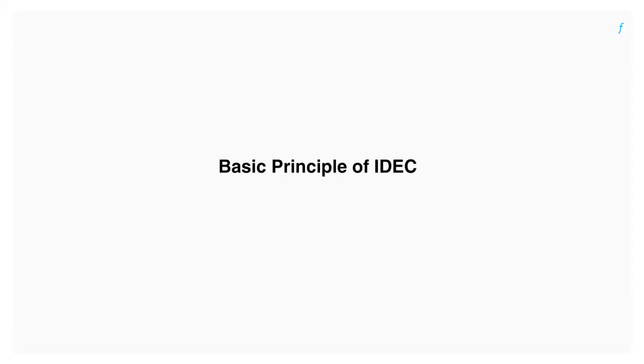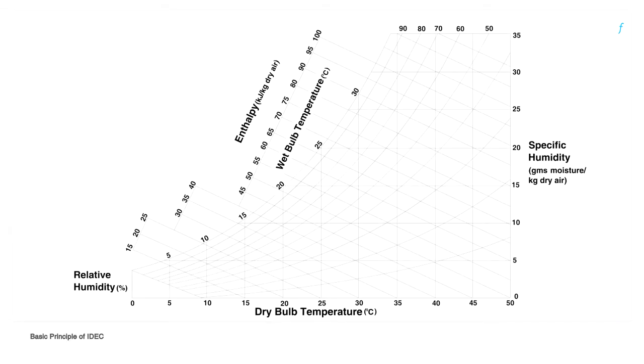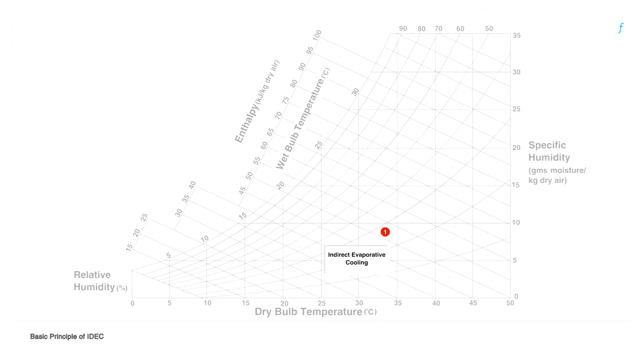The basic principle of indirect direct evaporative cooling can be understood using a psychrometric chart. Indirect direct evaporative cooling involves cooling warm air first with a sensible heat exchanger. This is the first stage or the indirect stage where sensible cooling takes place and we see a reduction in the dry bulb temperature without any change in humidity.